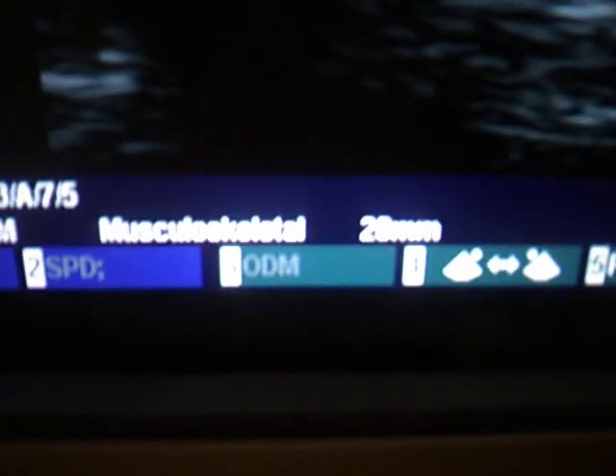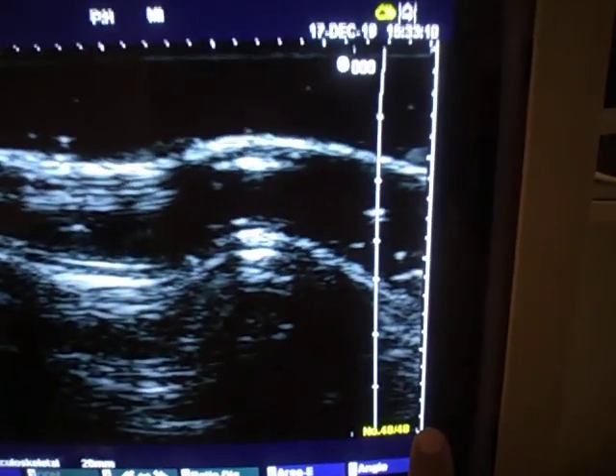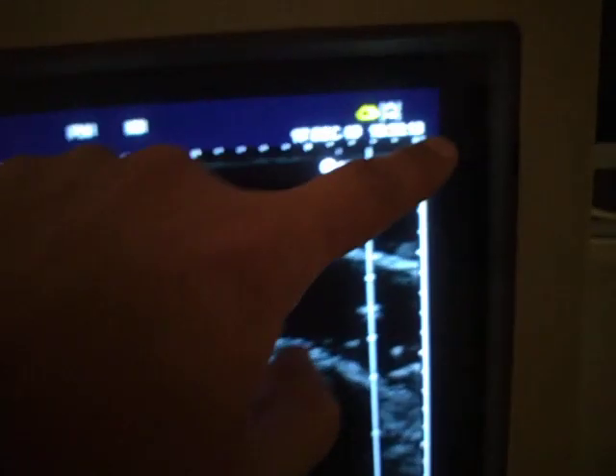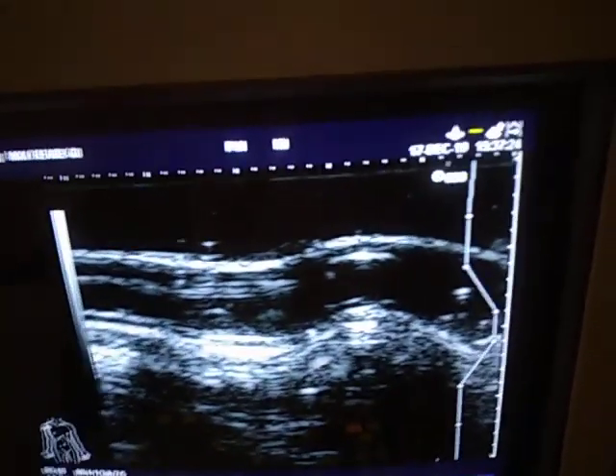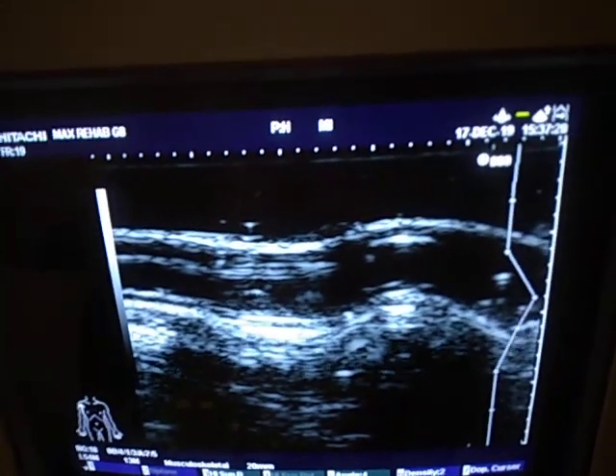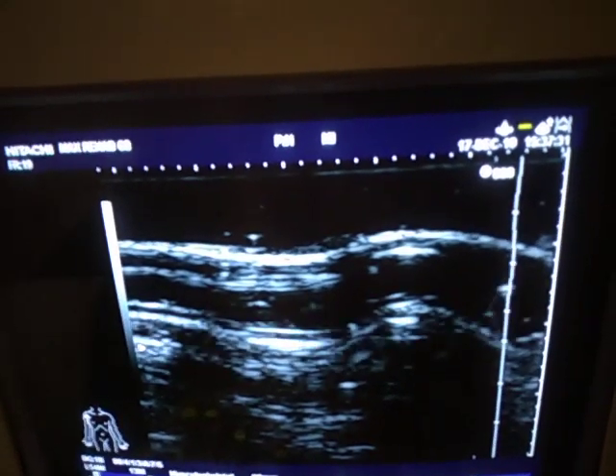Okay, so let's come down, and these fine lines, these markers, they are telling us about the depth. So we are working at 20 millimeters, and we can count all these lines, 1, 2, 3, 4, and all the way up. So there will be 20 lines. This line having these dots will be 1, 2, 3, 4, 5, 6, and these will be the TGC lines. So let me show you. If I move the TGC and unfreeze the image, see, the area will become brighter, and if I decrease the TGC, the area is becoming darker. So you can say it's just the returning echoes that the machine changes.